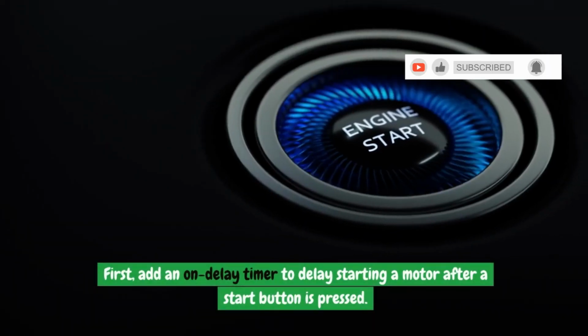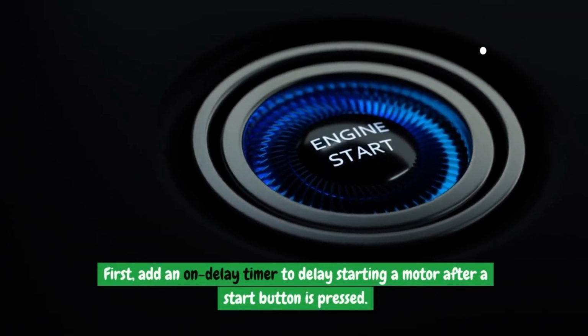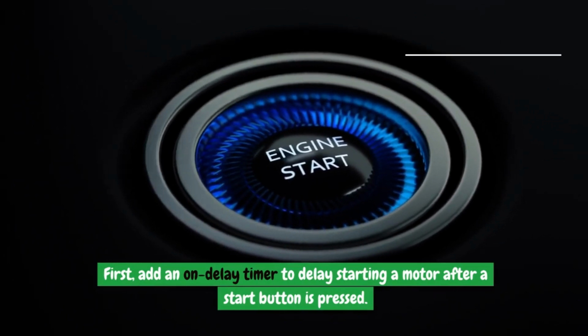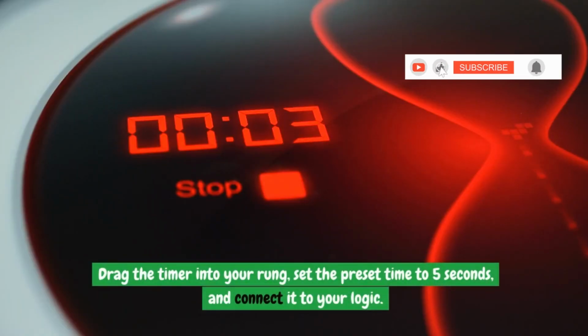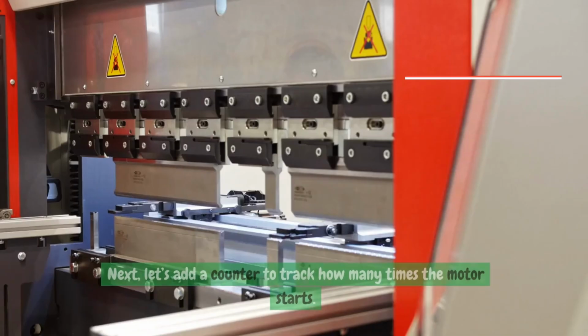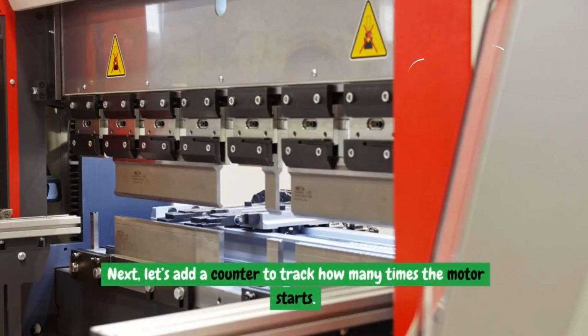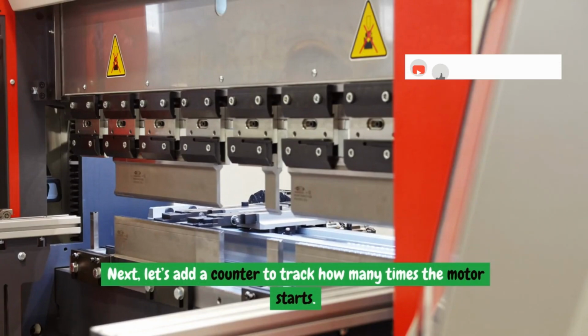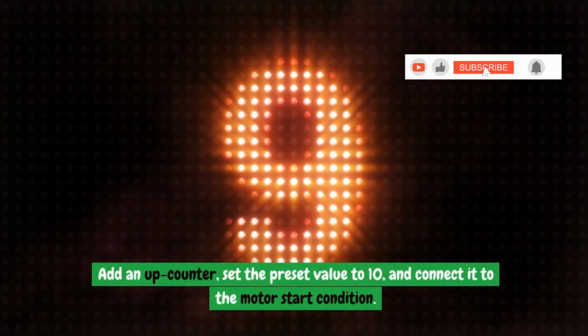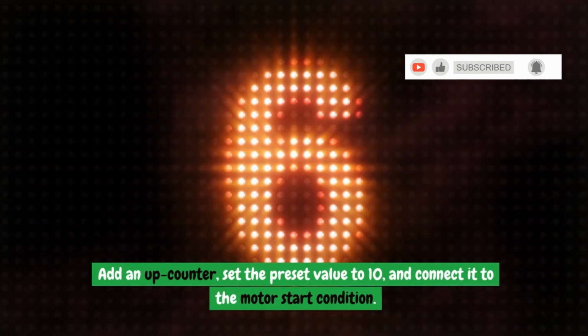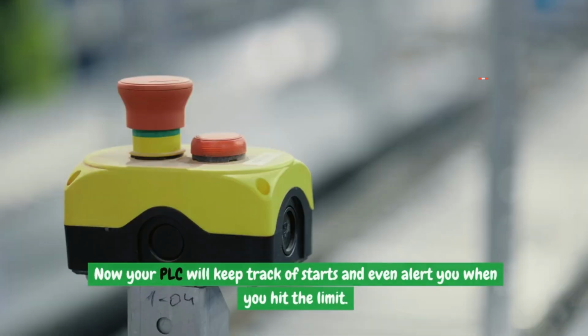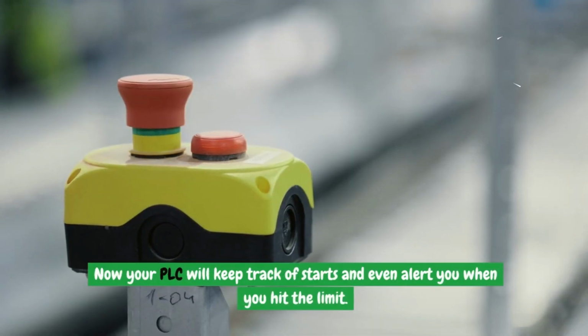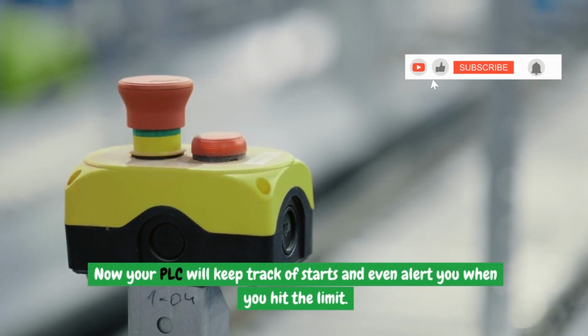First, add an on-delay timer to delay starting a motor after a start button is pressed. Drag the timer into your rung, set the preset time to 5 seconds, and connect it to your logic. Next, let's add a counter to track how many times the motor starts. Add an up counter, set the preset value to 10, and connect it to the motor start condition. Now your PLC will keep track of starts and even alert you when you hit the limit.